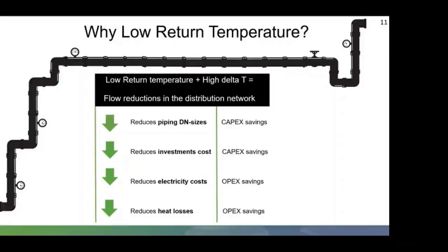With a mass flow at the lower temperature, there is less heat loss in the distribution network. Again, smaller pipework, good insulation, cheaper insulation because you're insulating smaller pipes. We must remember the distribution systems are running constantly. Another benefit of reduced return temperature is you can add new connections without replacing or increasing the pipe size. So the savings in the distribution system mean continuous savings for the energy and cost at all times.